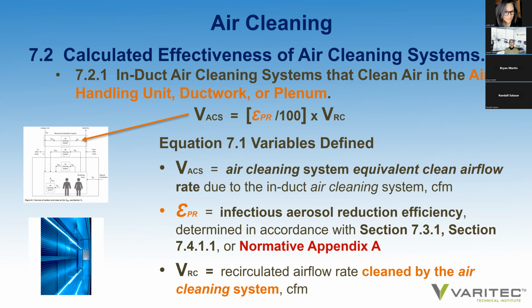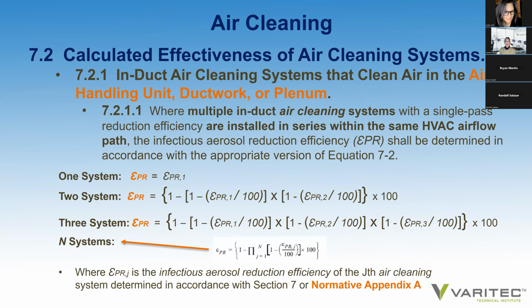So if we look at an in-duct air cleaning system to provide clean air from an air handler, ductwork or plenum, it's very simple. You take the infectious aerosol reduction efficiency, divide it by 100, times the amount of return air, and you will get the volume of clean air supplied by the unit to this space to see if it conforms to the requirement projected in the equivalent clean air table we discussed earlier.